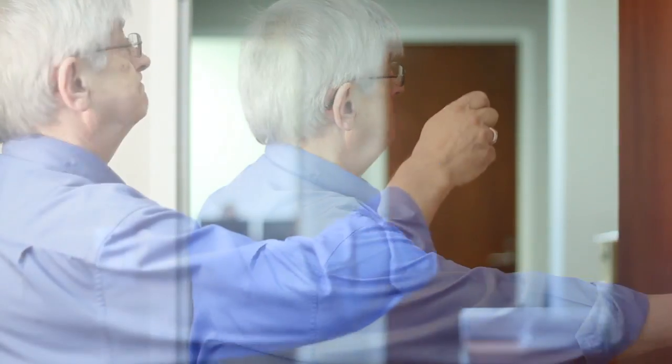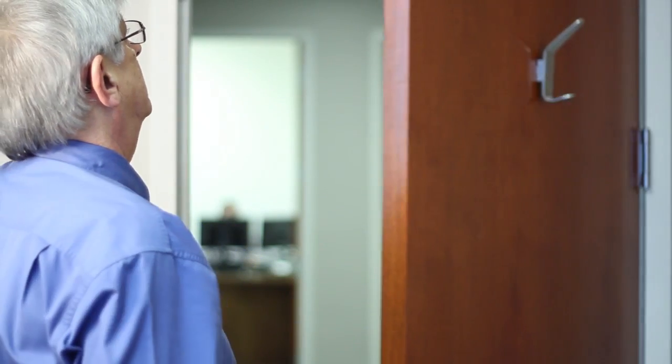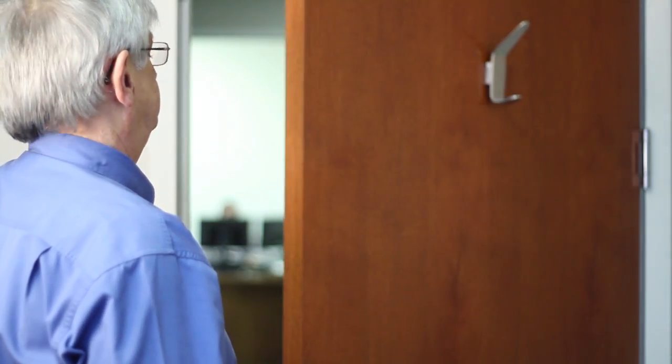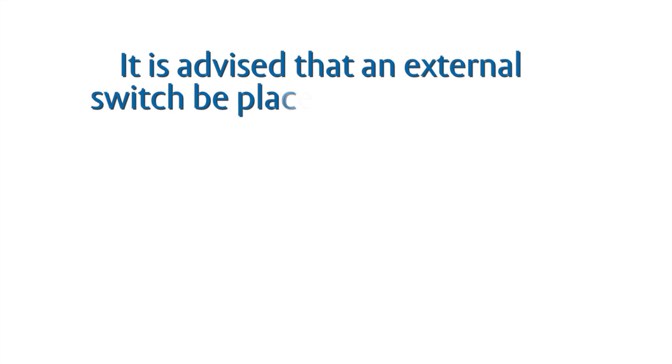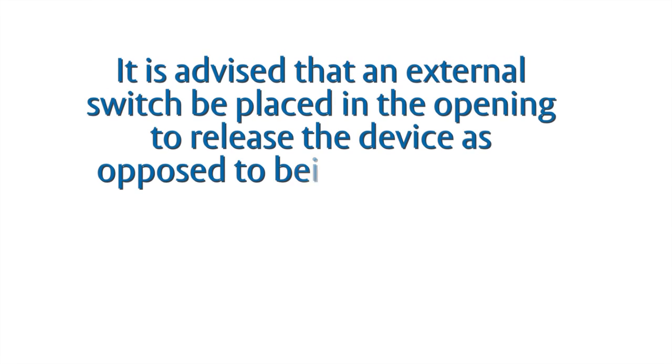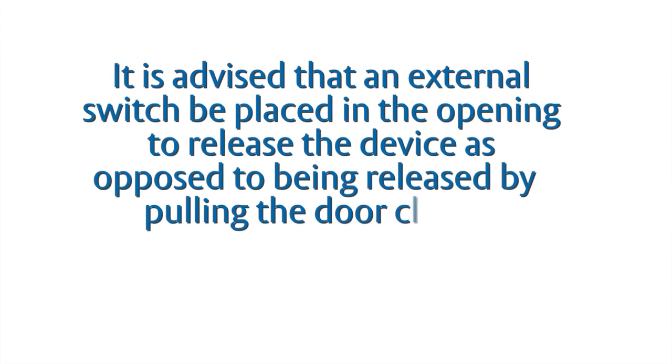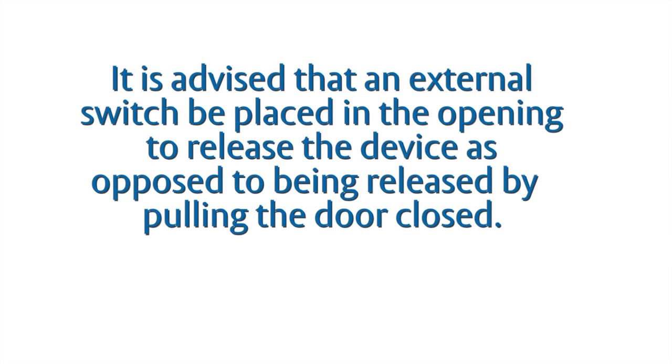It should be noted that in the event the door will be repeatedly released from the hold open position, it is advised that an external switch be placed in the opening to release the device, as opposed to being released by pulling the door closed.